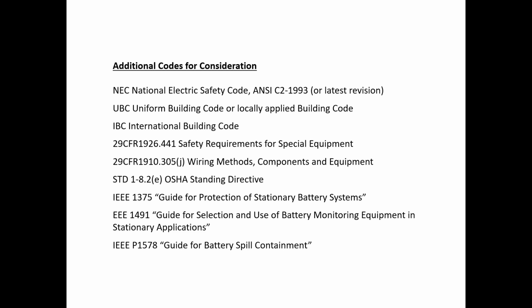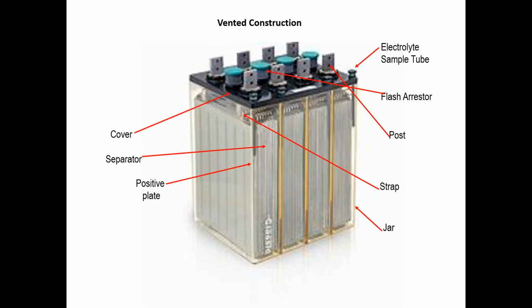Yeah, there's a lot of consideration when looking at a battery, and not only the battery but also the auxiliary. Some of seismic requirements for the racking or installation itself, how it gets anchored, spill containment, what's required there. So there's a lot of considerations that need to be taken into account when looking at the initial design or install. So this is a vented or flooded battery. This particular one is a 4-cell jar, so it's 8-volt, nominal 8-volt.